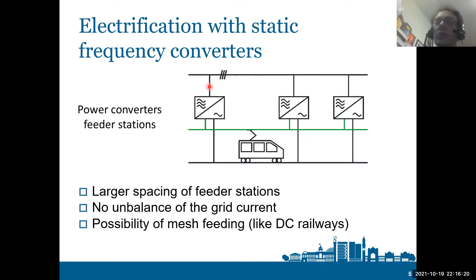There are a number of converter topologies for static frequency converters, which are reported here in this slide. All of them are, to some extent, multi-level topologies and modular topologies to reach the typical power of these substations, which range anywhere between 10 to 20 MVA. And the first topology is called the back-to-back topology.